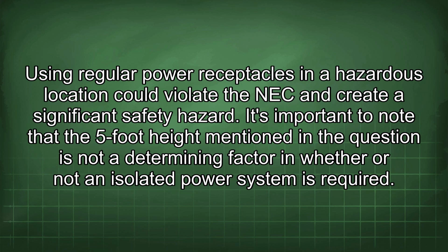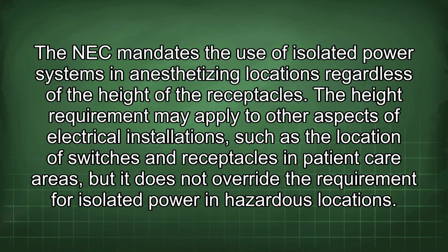It's important to note that the 5-foot height mentioned in the question is not a determining factor in whether or not an isolated power system is required. The NEC mandates the use of isolated power systems in anesthetizing locations regardless of the height of the receptacles. The height requirement may apply to other aspects of electrical installations, such as the location of switches and receptacles in patient care areas, but it does not override the requirement for isolated power in hazardous locations.